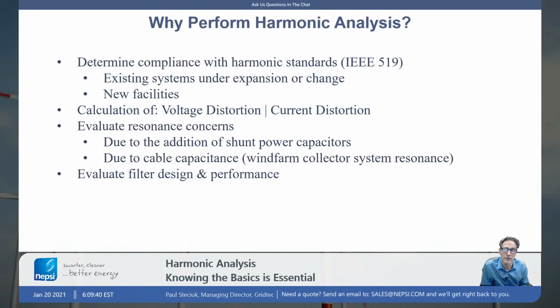So why perform harmonic analysis? First, you're looking to determine compliance with a harmonic standard. In North America, we're oftentimes talking about IEEE 519. In Australia, you have your own standards. So you're conducting harmonic analysis to determine if your facility, whether it's a renewables plant or a mine, is compliant with some harmonic standard. You might be thinking about expanding an existing facility, or you might have an entirely new facility. Harmonic analysis allows you to predict the performance of your system. Do you meet the harmonic standards?